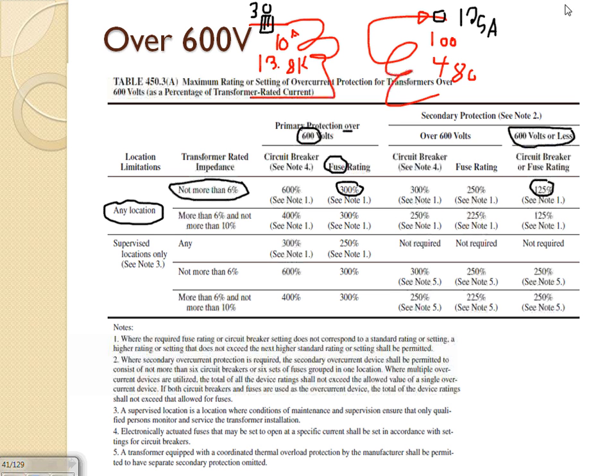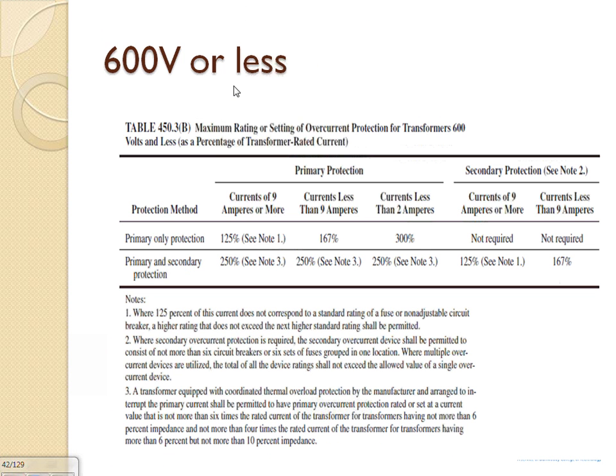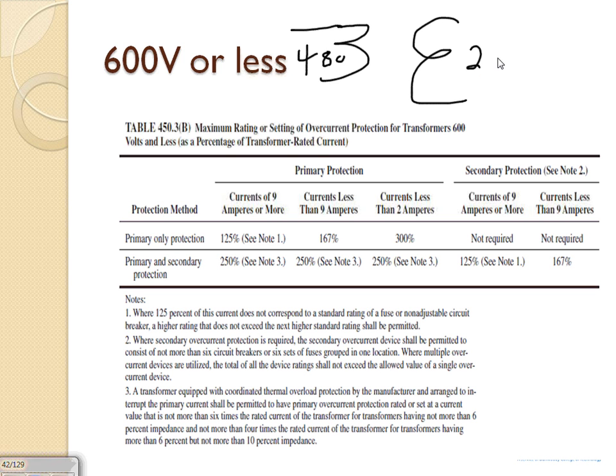This is this table. If you go to the second one, this table is very common for you guys. I know you use it all the time. This is if you have a 480 system here and on the secondary you have 208. Very common application. 480 on the primary and 208 on the secondary, to feed your receptacles and some lights. You want to burn your lights at 120. This table is only used if the whole system is 600 volts or less, both primary and secondary. That's where you use it.